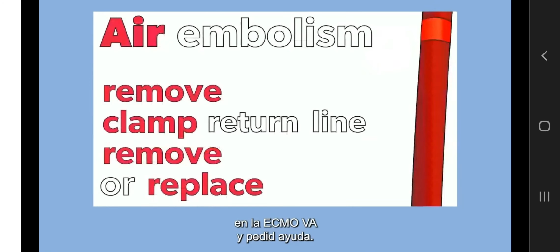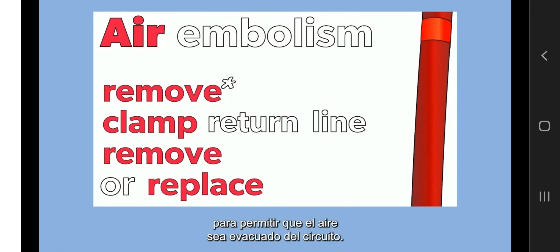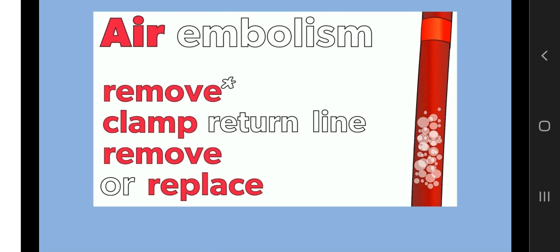After clamping the return line, you could try to remove the air from the circuit using gravity to facilitate the movement of air to the nearest stopcock, removing the pump head or the membrane lung or both from their housings. No clamp needs to be placed on the drainage line to allow for air to be evacuated from the circuit. When air removal is unfeasible or unsuccessful, you may need to replace the whole circuit if extracorporeal life support is still needed. After complete de-airing or circuit replacement and after the air source is detected and fixed, ECMO support may be resumed.